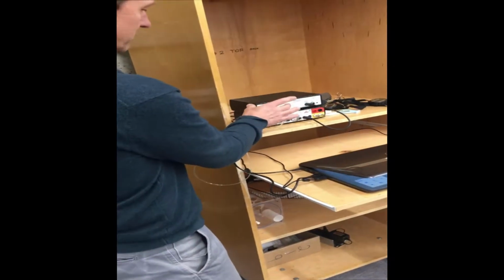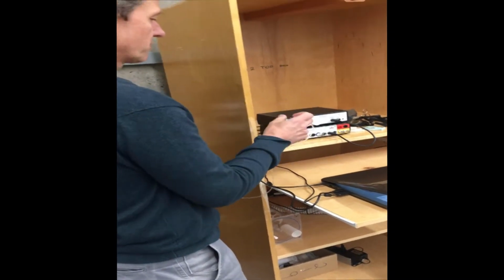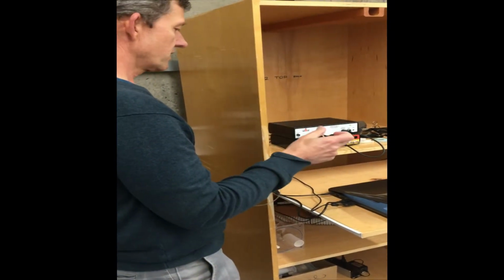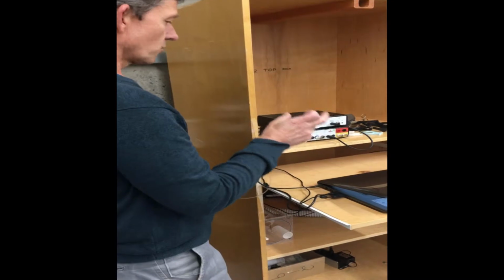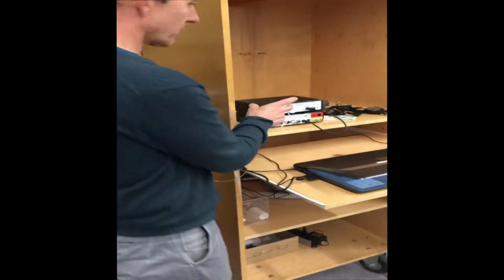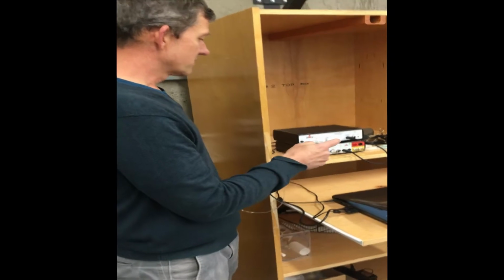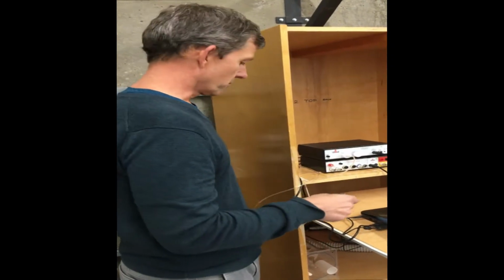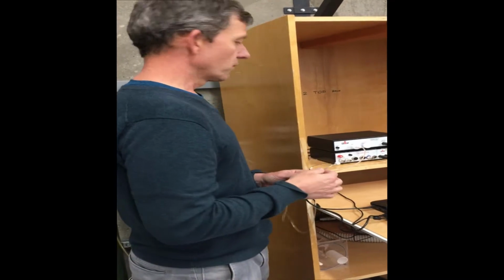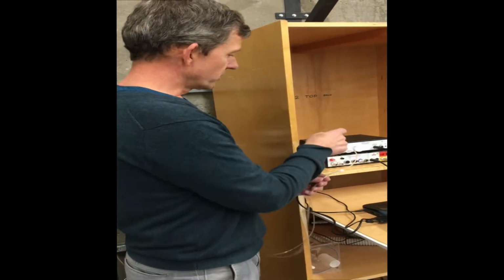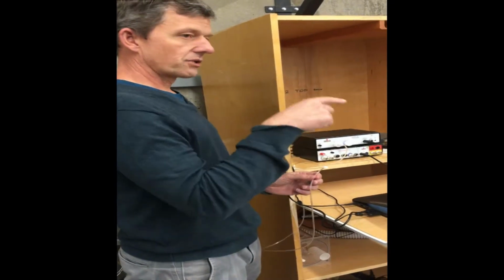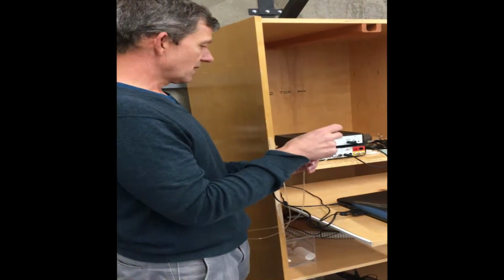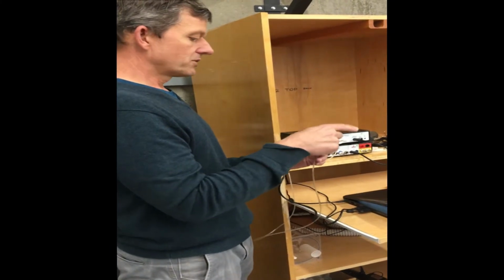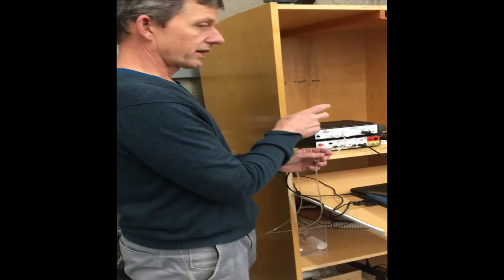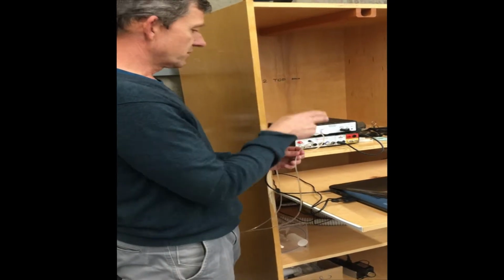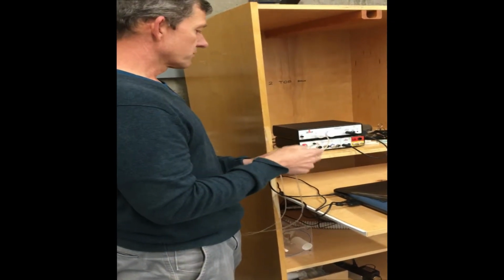The nice thing about this is it's very compact. It also has two different sensors in it: a sensor for carbon dioxide and a sensor for oxygen. So it works out extremely well. You can probably hear that it's making a noise, and the reason for that is there's a pump inside that draws the sample through. It's sampling at a rate of 200 milliliters per minute. In order for you to get the sample into the gas analyzer, it has to move through. So if you breathe in or if you're sampling something, you want a pretty good time between when you blow into it, or when it samples, to when it registers. So it's drawing air through continuously at 200 milliliters per minute in order to sample that.